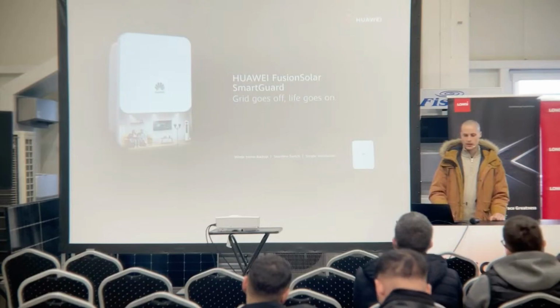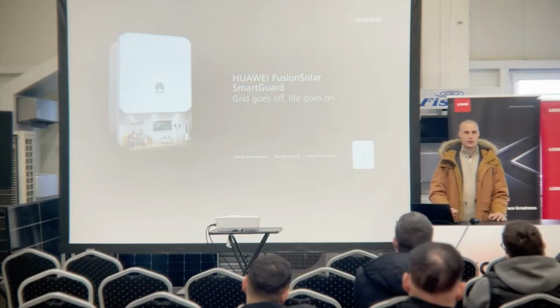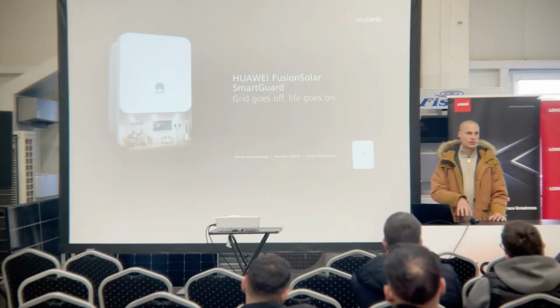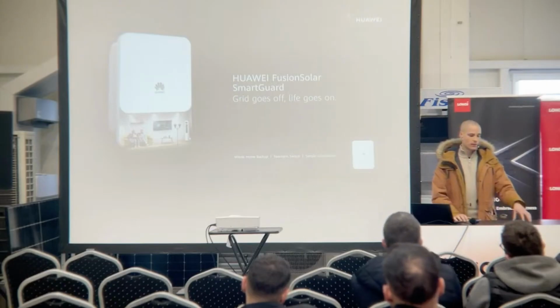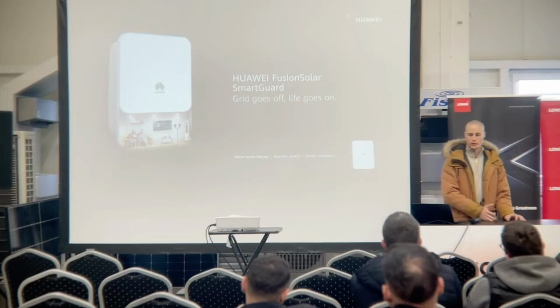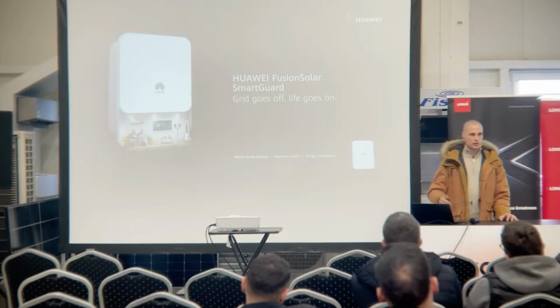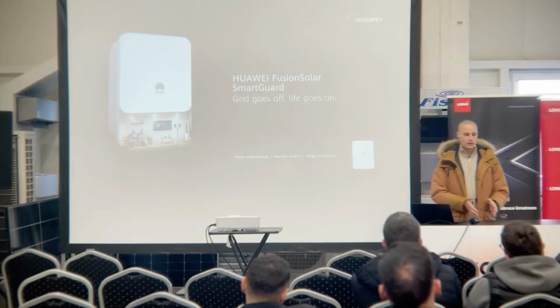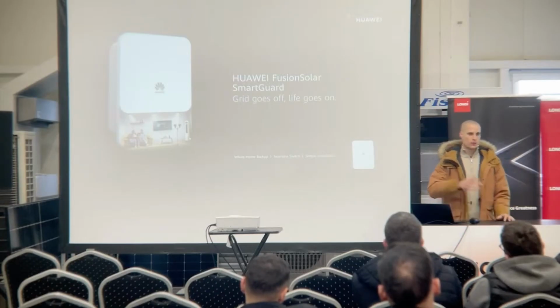With SmartGuard, the whole wiring is different, because you have to install it between the electricity meter and the home junction box, in between and in front of everything. You have to wire the whole house through the SmartGuard, and when the grid has an outage and you don't have electricity, the SmartGuard switches off the whole grid and powers the whole house from the inverter.